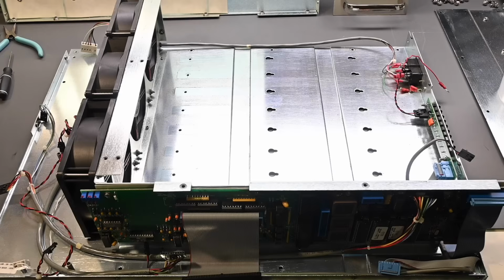So when I received it, I took the top cover off, had a look around inside. It was extremely dusty and dirty. Went ahead and powered it up, and it seems to work okay. So there really won't be troubleshooting because I don't see any issues going on. But like all the test equipment that I get in, I always like to take it apart and clean things up and really inspect it and check things out and make sure everything's in good condition, just a good thorough visual inspection. And sometimes that means quite a bit of work, but oftentimes it's worth it because you'll come across some issues and things that might be hidden.